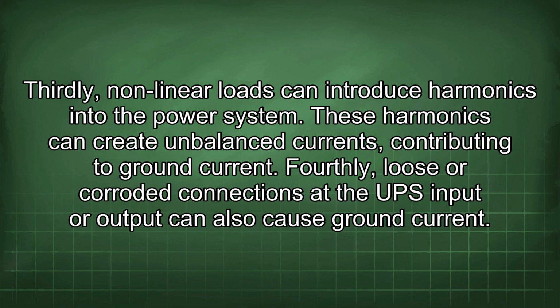Thirdly, nonlinear loads can introduce harmonics into the power system. These harmonics can create unbalanced currents, contributing to ground current. Fourthly, loose or corroded connections at the UPS input or output can also cause ground current.